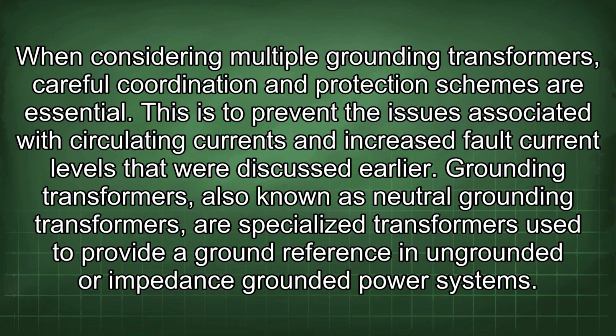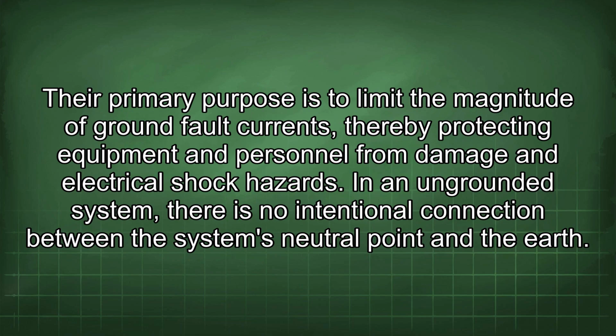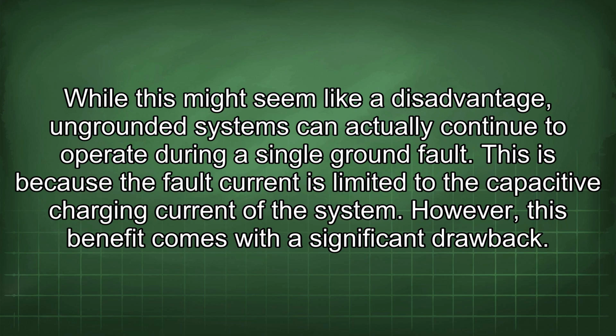Grounding transformers, also known as neutral grounding transformers, are specialized transformers used to provide ground reference in ungrounded or impedance-grounded power systems. Their primary purpose is to limit the magnitude of ground fault currents, thereby protecting equipment and personnel from damage and electrical shock hazards. In an ungrounded system, there is no intentional connection between the system's neutral point and the earth. While this might seem like a disadvantage, ungrounded systems can actually continue to operate during a single ground fault. This is because the fault current is limited to the capacitive charging current of the system.